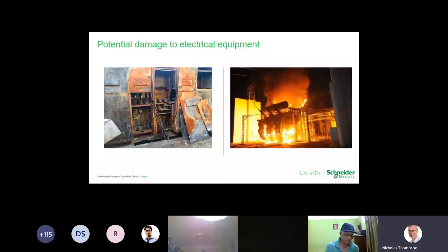So what we want to start to think about is what potentially may happen. These two images here, again sourced from Google, are very extreme, but if we don't do something about the fault in a relatively short space of time, that's literally what could occur. The switchgear on the left could be replaced in a relatively short space of time, in say weeks or maybe months, but the transformer on the right, which on the face of it looks to be a 66 or 33 kV step down transformer, may take many months to get replaced, and may potentially cause significant downturns and outages in supply.